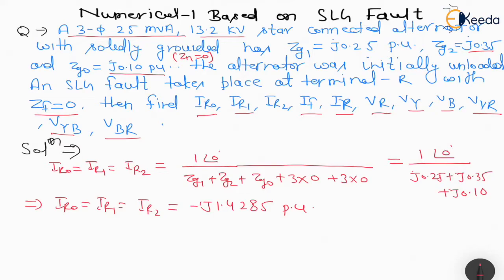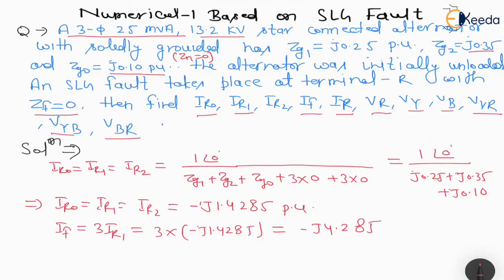So this is the value of IR0, IR1, and IR2. Now if we want to find out the fault current IF, then IF = 3 × IR1 = 3 × (-J1.4285) = -J4.285 per unit. This is how we calculated the fault current.